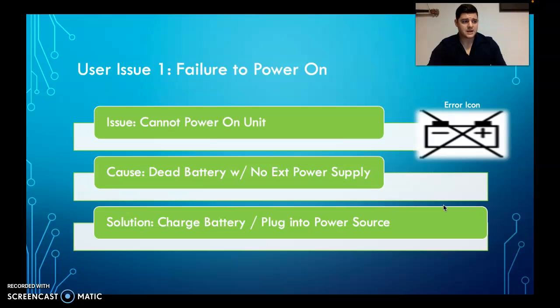As far as mitigating future issues, we're just going to inform the clinician of the actual battery life of that unit. We'll try to walk them through the user manual with the error icon pictures, graphics, and illustrations, and show the several ones that they could see working with this unit, and then what the simple fixes are for those. So in this case, dead battery, charge the battery. Pretty straightforward. There was no equipment needed really outside of what the device had, which was the power cord. So there's no purchase request needed, no need to put in any order requests for extra parts.